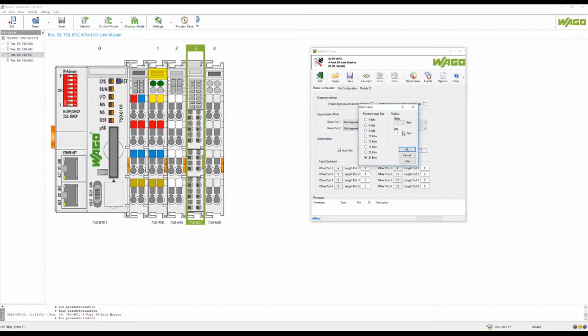This is important because when you go in PLC and look for the data coming back, you need to count that you have a status byte, 2 bytes of mailbox, and 1 byte of SIO. And after that, you're gonna get this byte for the light and 4 bytes for the encoder. We're gonna see that in a second.